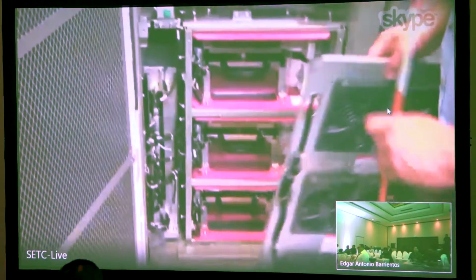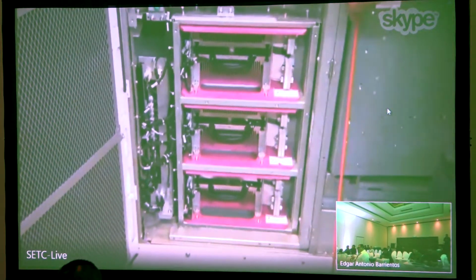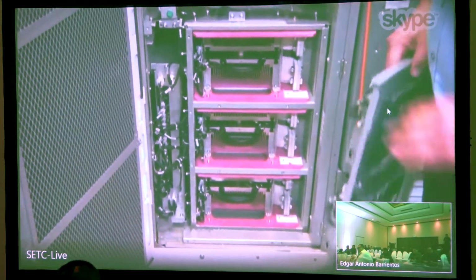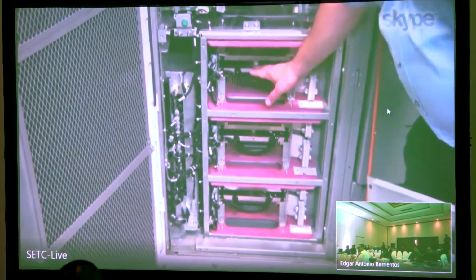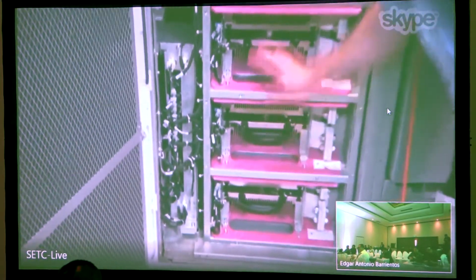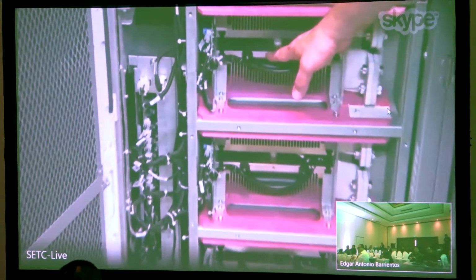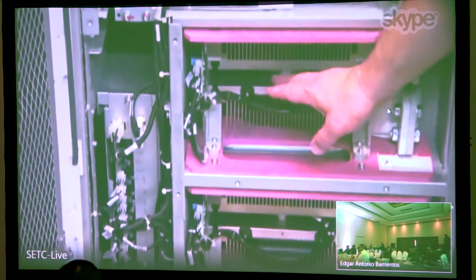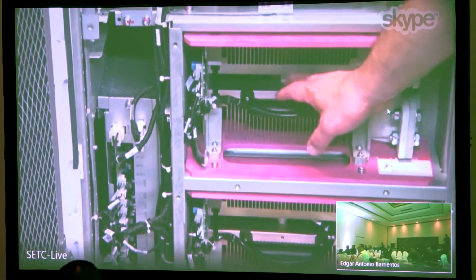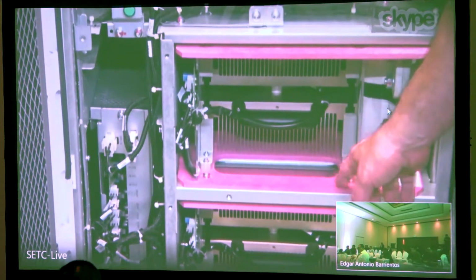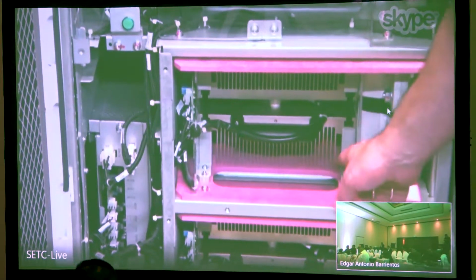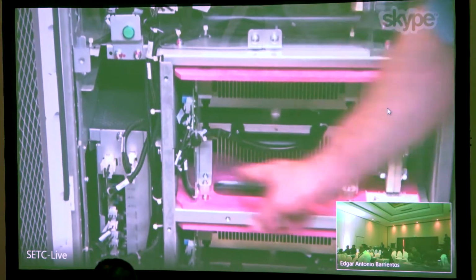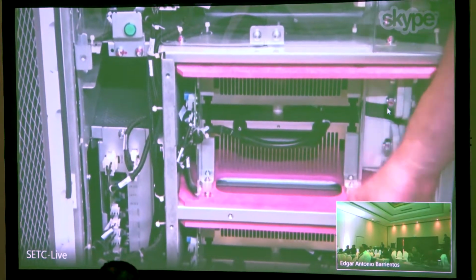When we pull off the fan door, the first thing we see is the static bypass, the semiconductors for the static bypass here. These are very modular and can be pulled in and out if required, just by removing a couple of screws and bolts to the bus.